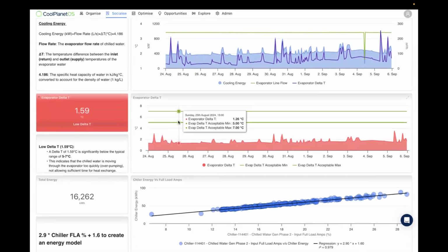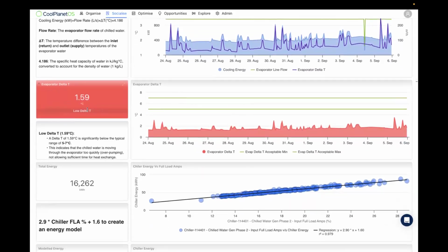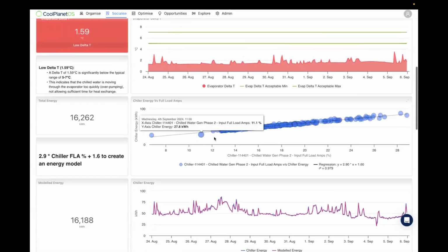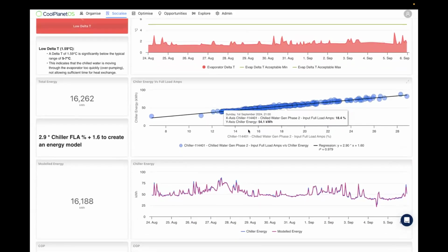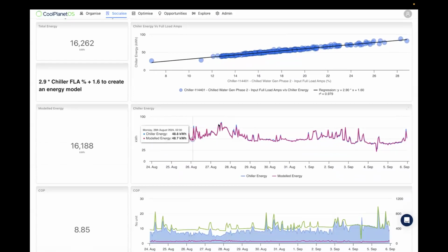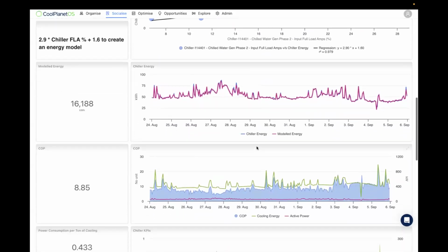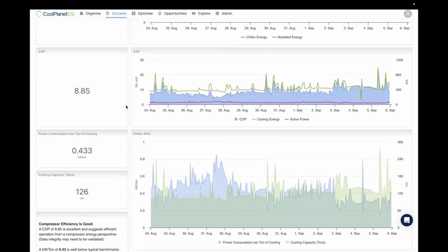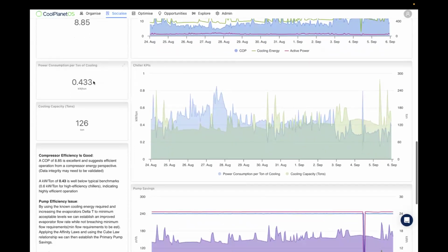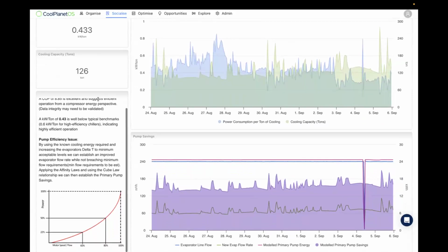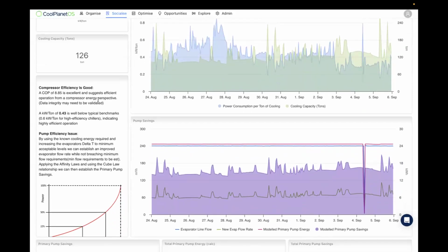So they're looking at nominal analysis procedures like the evaporator delta T, generating linear regression models using two variables, visualizing that model against actual, and looking at other KPIs to validate previous analysis. So the COP of the system, the power consumption per ton of cooling, and the cooling capacity in tons. And then the real power output comes from the AI in combination with the SME.